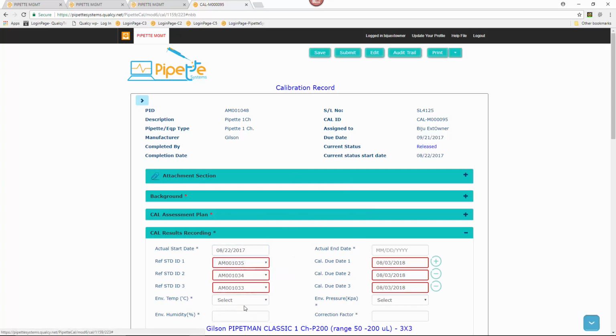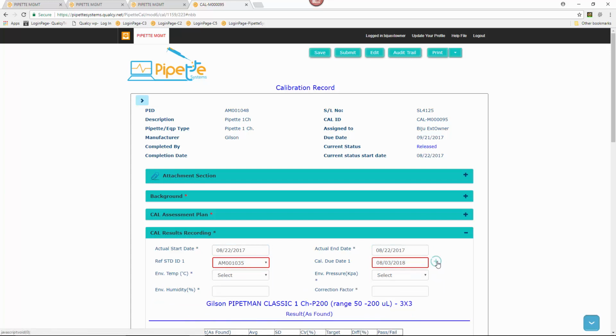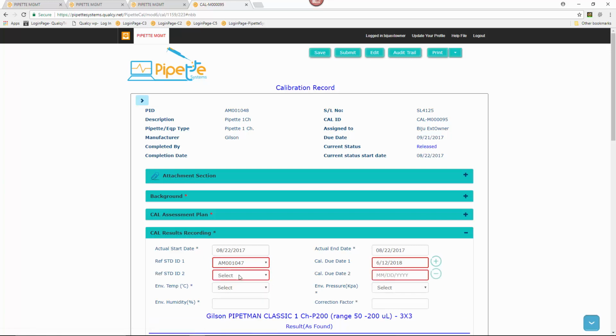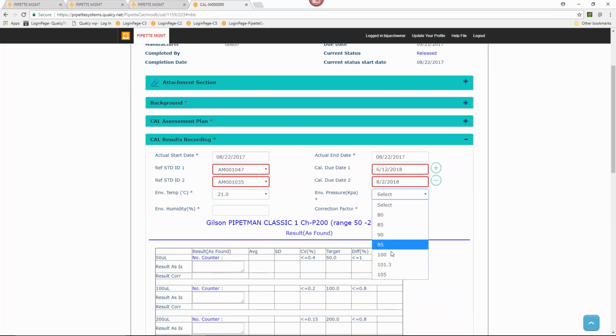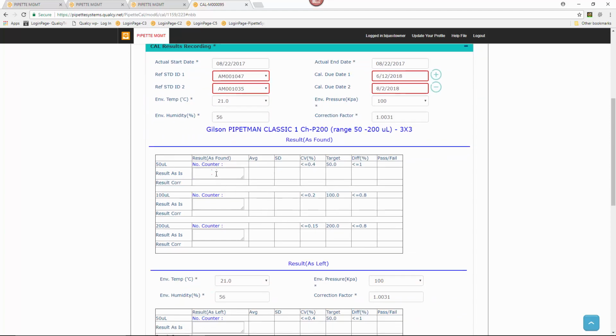So as you can see, the reference standards have automatically been taken from the previous records, or you can remove them. You can add them. The one that we added was 147, so I can add that one. So if I need to add another reference standard, I can select it. And the temperature, today's temperature and the pressure, I can select based on the available data. So humidity, let me fill in some things. And here, let's say I'm going to do only as found data. I will skip the as left data.